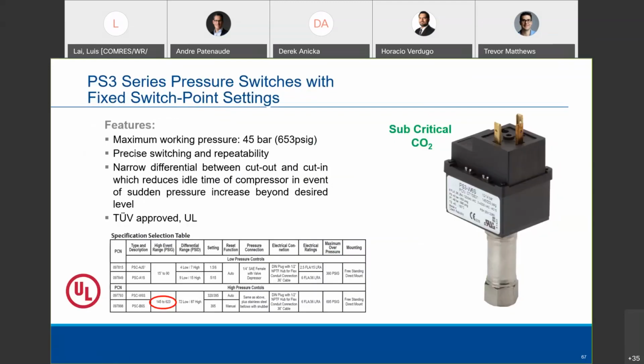For the low pressure side, so suction, medium temp suction, or subcritical discharge, here's the model, PS3 or PSC. Apologize for the confusion, keep flipping back and forth. You can see the PSC W6S is rated up to 653 pounds. So that's plenty, lots of pressure, even on the low side and the high side. You've got auto reset, manual reset, and with the different freestanding is really what we're looking at here. Freestanding screws onto a Schrader valve.